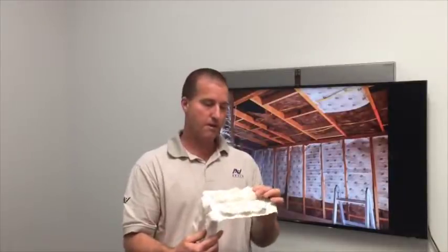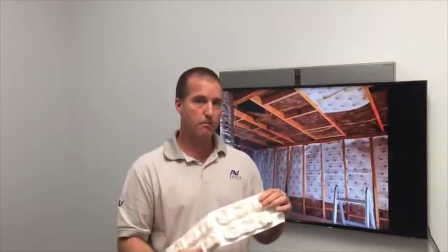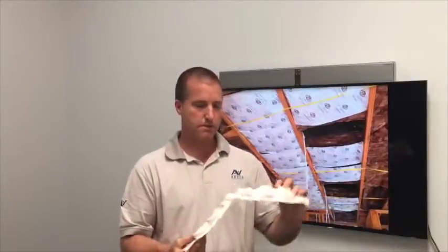Typically we recommend about 1 kilogram per cubic metre of air, up to 2 kilograms per cubic metre of air. So it comes in different sheets, all the way from 1.5 kilos per square metre up to 10 kilos per square metre, and you can decide how many square metres suits your building application. As a general rule of thumb, use that 1 kilo to 2 kilos per cubic metre of air, or you can do a more detailed calculation using software. So if you need help with it, let us know, and that's all from me for now.